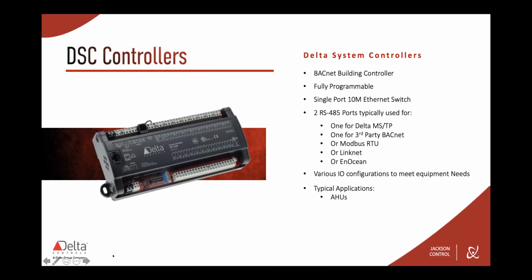Again, supports Modbus RTU. Now we also have a proprietary protocol called LinkNet. And basically that is connecting to some of our temperature sensors, our smart stats, or expanded IO devices as well. So it gives you the flexibility of either adding extra IO directly onto this controller or in the same cabinet, or you can network them out.